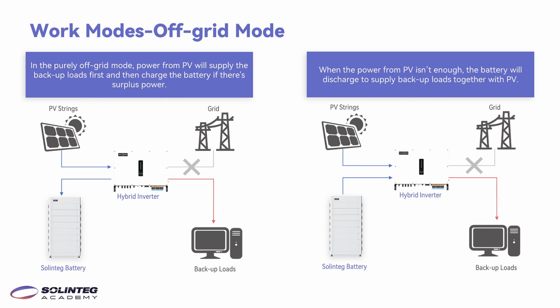The last work mode is off-grid mode, usually used in some places where there is no grid for a long time. So this is a purely off-grid mode. The power from PV will supply the backup loads first and then charge the battery if there is any surplus power. When the power from PV isn't enough, the battery will discharge to supply the backup loads together with PV. For all the work modes, you can set them through the inverter's display, in our applications, or in the web monitoring. If you don't know how to set it, you can contact us.